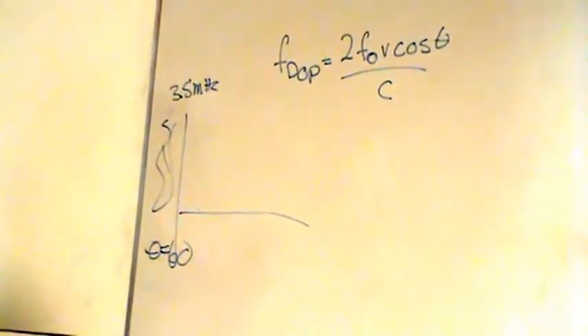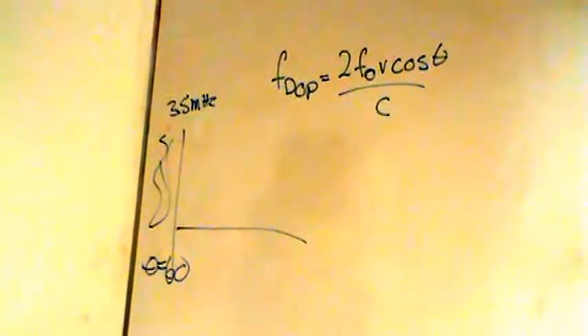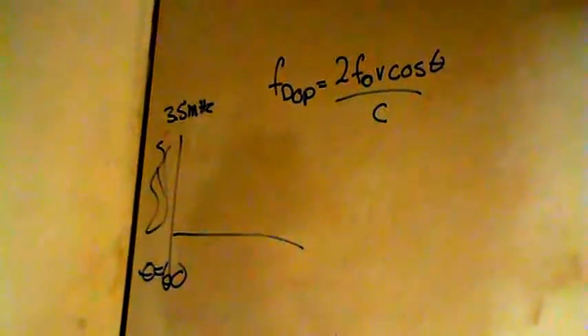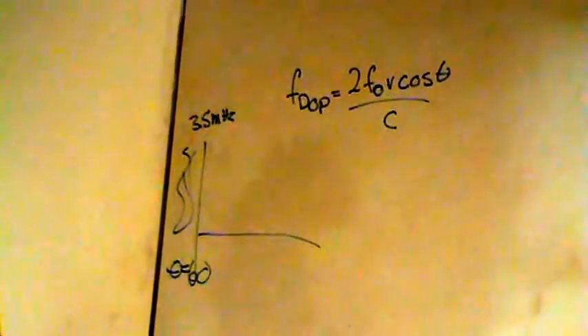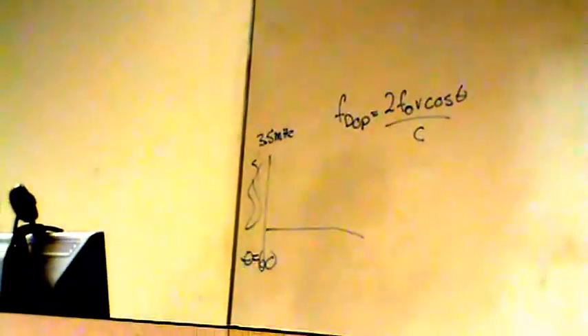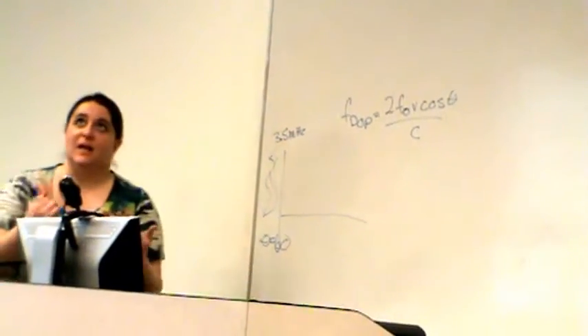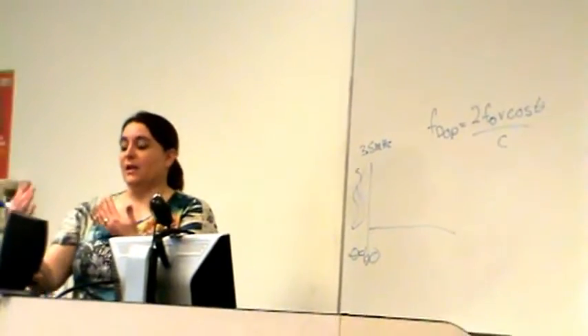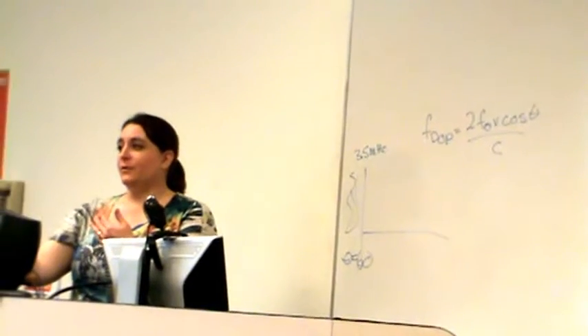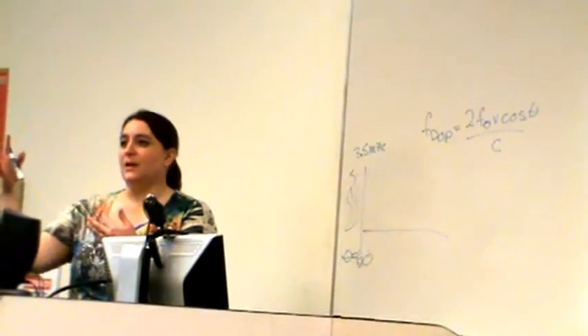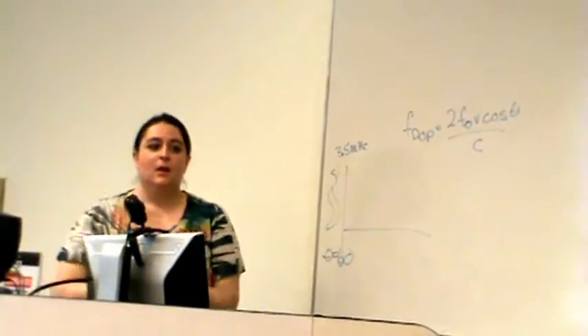The Doppler frequency that it's doing Doppler at is always lower than the imaging frequency. We always do Doppler at a lower frequency because of this whole idea of sensitivity. Because Rayleigh scatterers are such weak reflectors, if we did Doppler at a higher frequency, those weak reflections would be attenuated out, and we wouldn't get any Doppler signal. So we always do Doppler at a lower frequency.